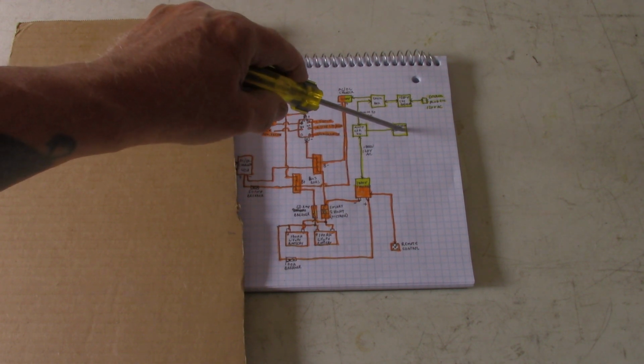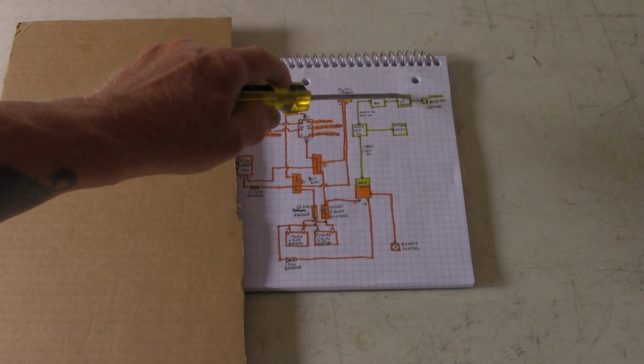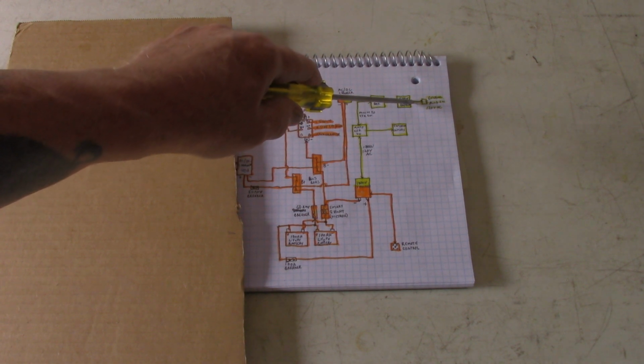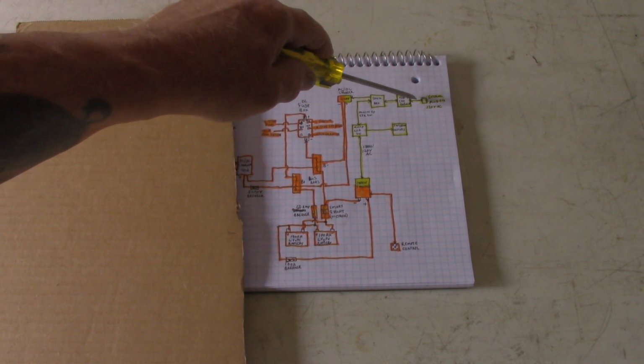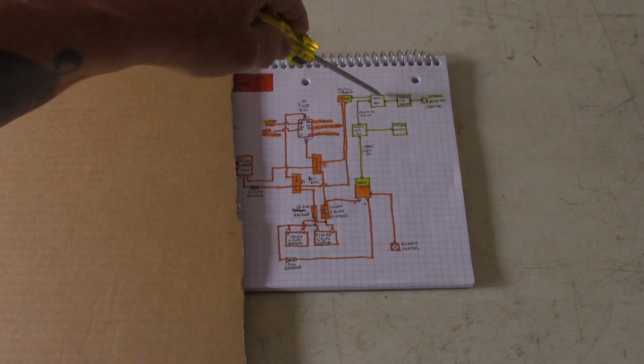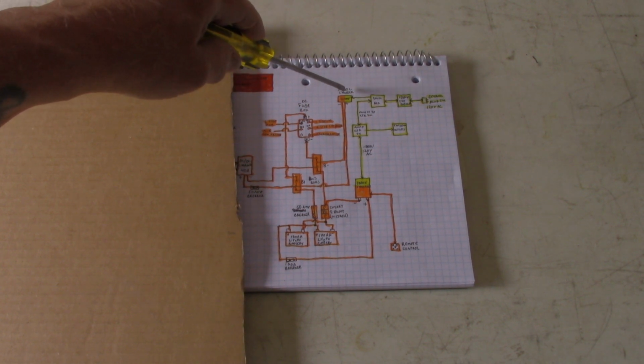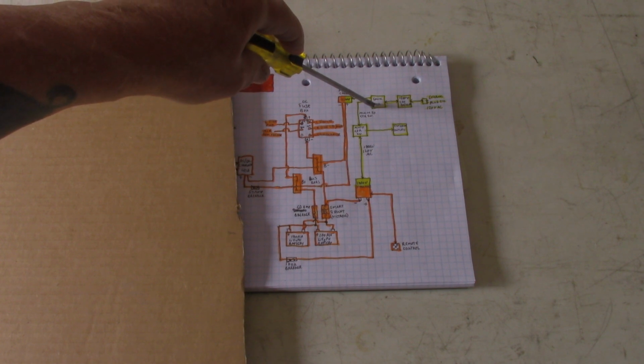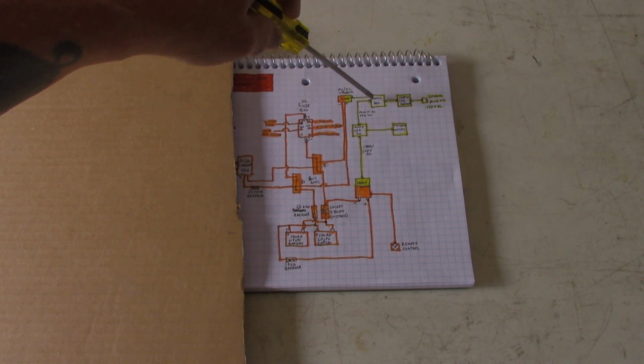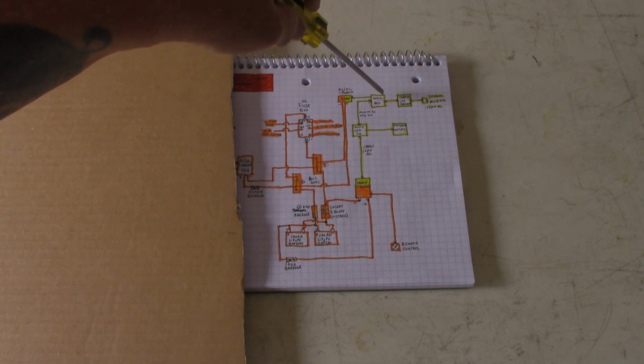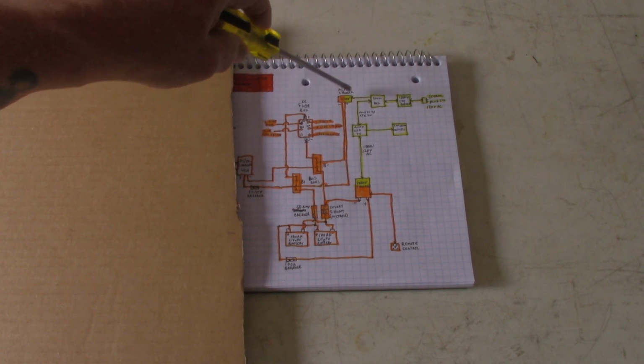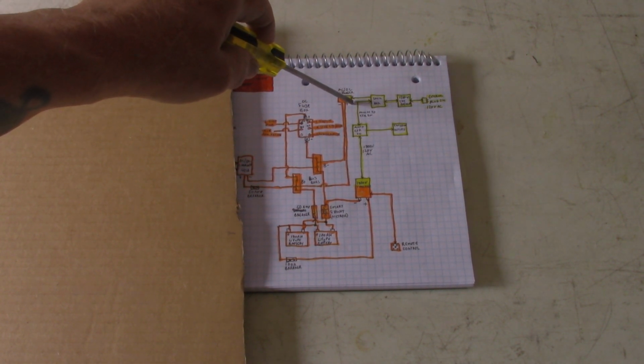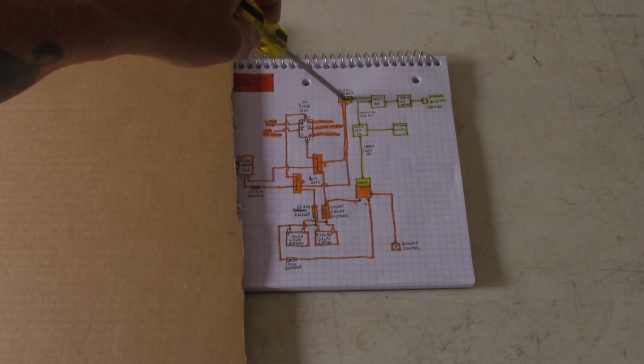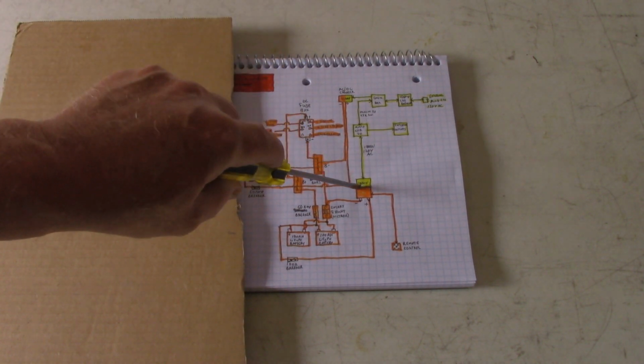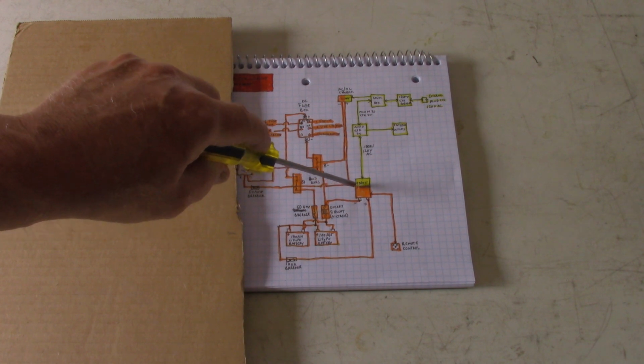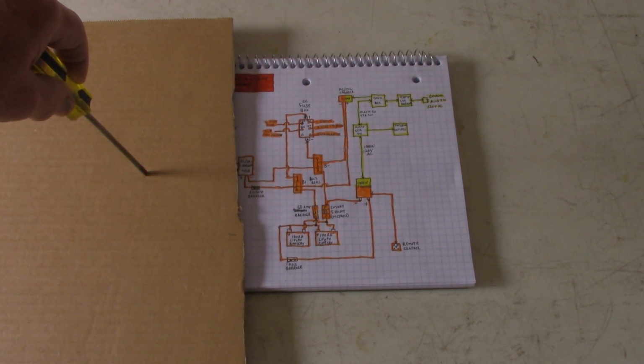Very simple, only got 3 major things to install. Well, 4 if you count this circuit breaker, which is already installed from the original basic install. So we'll put in a 15 amp circuit breaker in line with the power source. And this is a little connection box - you always have to use a connection box with 120 volt circuits, you can't just tape them together like we do with 12 volt DC. So, connection box, and now it's going to split into 2, so we'll provide power to the 30 amp charger and down to the switch. So we have the circuit breaker, the 30 amp charger, the switch, and the inverter - those are the things we're going to install. Okay, you've seen the plan, it's time to go do it.